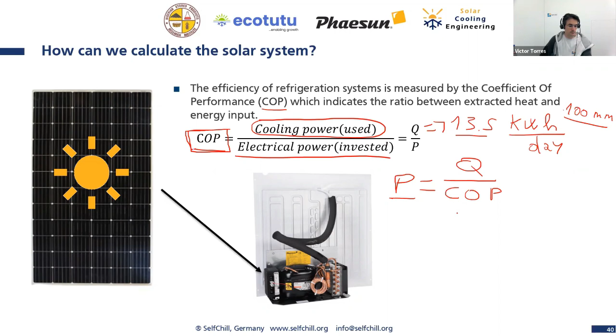We will continue with the equations of the COP. COP is the cooling energy divided by the electrical power, right? And if you remember from the last webinar, we said we can calculate the ideal COP, the Carnot COP, if you remember. This is depending on the warm temperature and the cold temperature, so the ambient temperature and the temperature inside the cold room, or in our case, the temperature in the water chiller, which is the place where we are creating the energy.